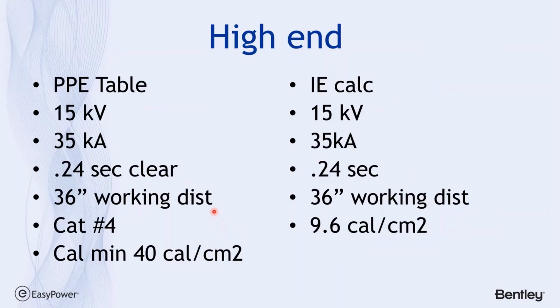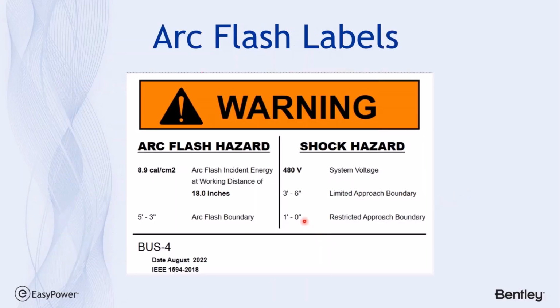So that was on the low end. Same thing was true on the high end. Whereas at 15 kV and 35 kA, we had a minimum 40 calorie exposure, just using the model, it was 9.6 calories per square centimeter. Now again, this can be put on the label if I want, but bear in mind that it says non-compliant with NFPA 70E specifically.